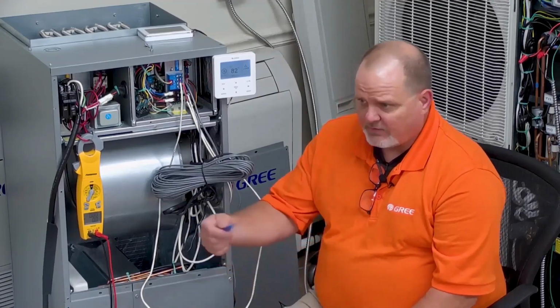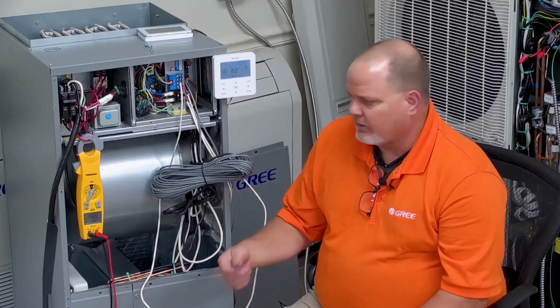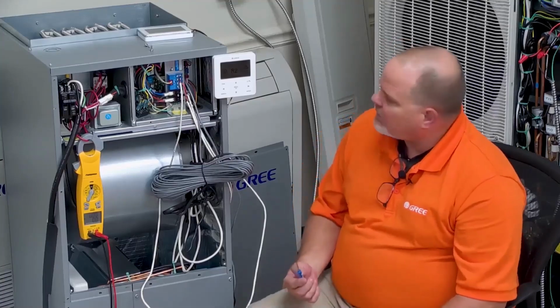And then I also want to demonstrate that it'll work with the power off. I'll just kill the power to the outdoor unit. What I can't demonstrate for you, or I'm not going to demonstrate for you in this video, is the auxiliary heat function. Because then you've got to have the heat pump running, and then the temperature's got to be within a degree or whatever, however the differential we set, and bring on the electric heat as well. The only reason why I'm not doing that, as you can well see here, is I don't have this thing refrigerant piped up yet. So once we get an air handler set up in here, and a couple other indoor units, we're going to have a fully functional system where I can run the heat pump and then be able to bring on the electric heat. I will have all that where I can demonstrate it. It does work, I know that, because I've got it on my own system at home.